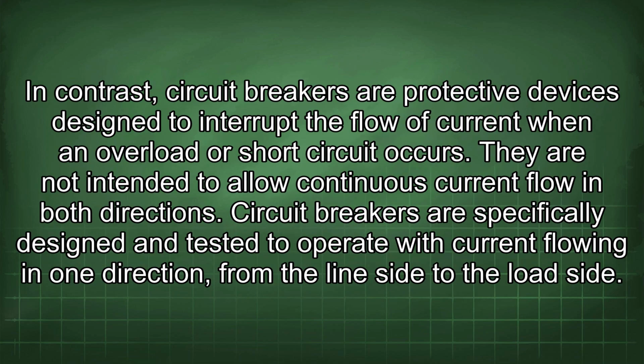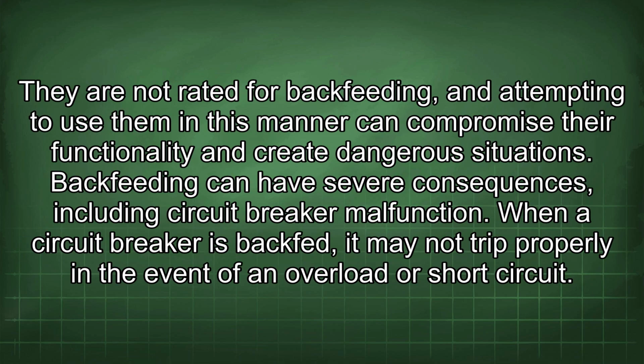In contrast, circuit breakers are protective devices designed to interrupt the flow of current when an overload or short circuit occurs. They are not intended to allow continuous current flow in both directions. Circuit breakers are specifically designed and tested to operate with current flowing in one direction from the line side to the load side. They are not rated for backfeeding, and attempting to use them in this manner can compromise their functionality and create dangerous situations.